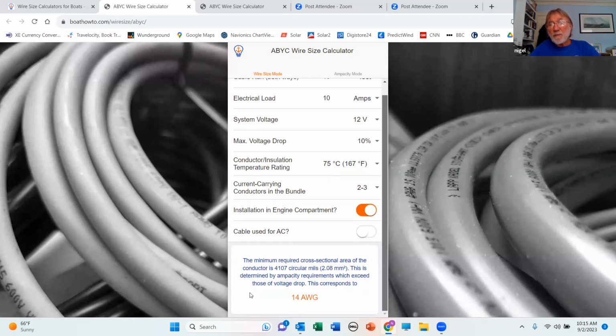I've reduced the length of the run, which means the voltage drop goes down, because the voltage drop is cumulative over the length of the run. And we've got to a point now where the voltage drop is not driving the process, the ampacity is driving it. So we have to put a larger conductor in.